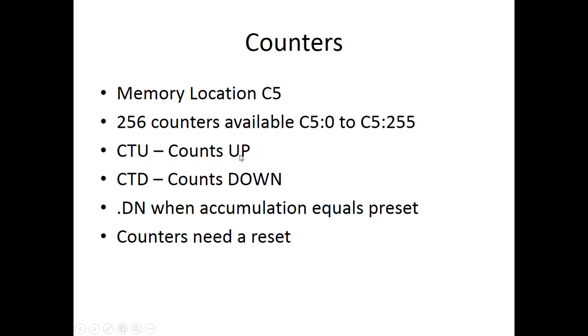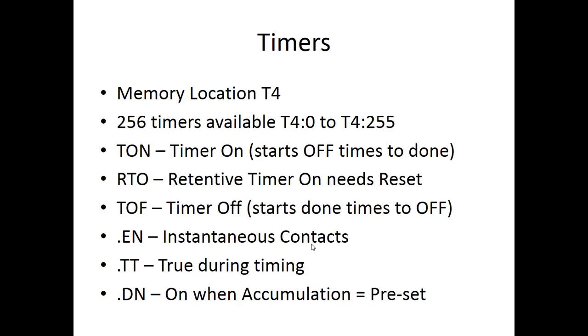The counters are retentive, which means that they need a reset. So if you lose power to the CPU or something like that, when you turn it back on, the counter will remember the accumulation number. Reset, RES, will reset it.